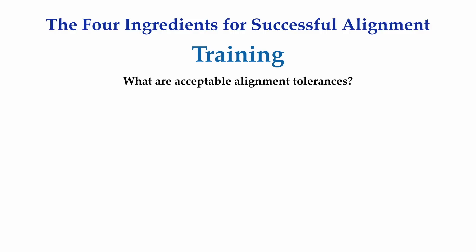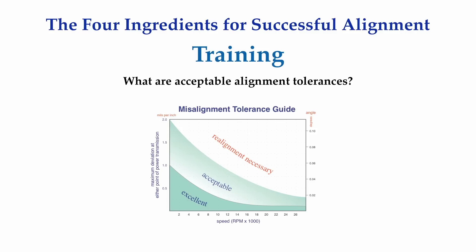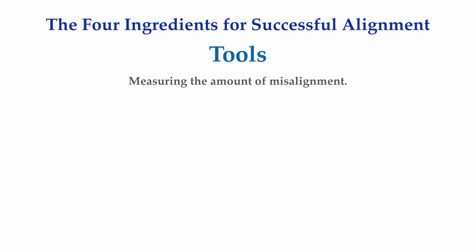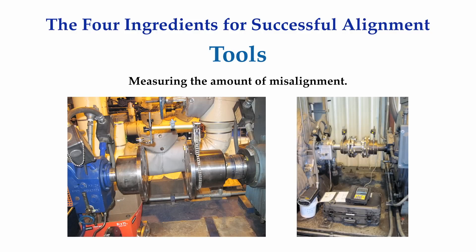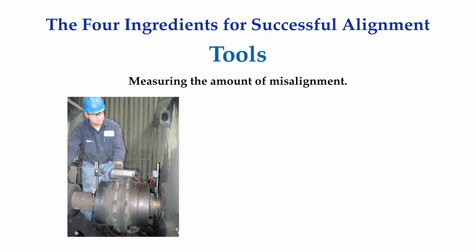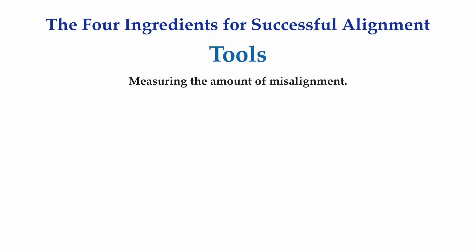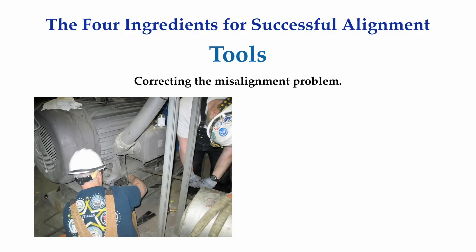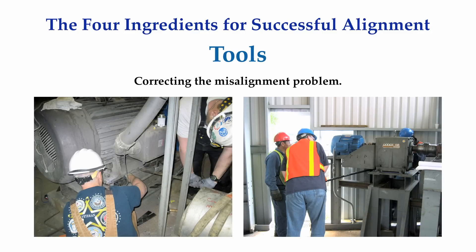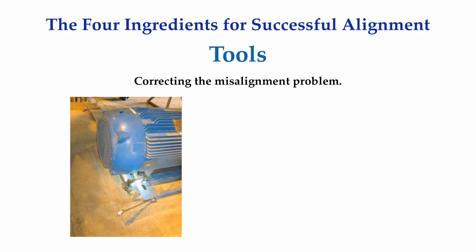Perfect alignment in the real world is virtually impossible to achieve. It is important to understand what is an acceptable amount of misalignment and the difference between coupling tolerances and alignment tolerances. When you hear about alignment tools, usually the first thing that comes to mind are alignment measuring tools, like dial indicators and laser detector systems. But dial indicators or lasers have never actually aligned any piece of machinery — all they do is measure the amount of misalignment. You will also need tools to loosen foot bolts, safely lift machines, add or remove shim stock, and precisely move machinery sideways or axially.